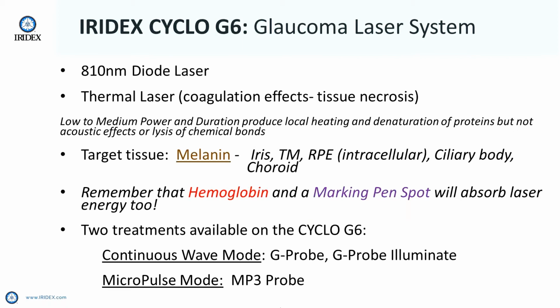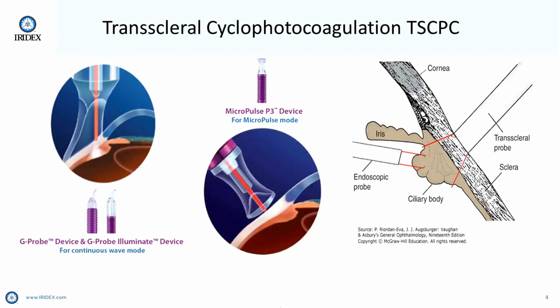There are 2 treatments available on the Cyclo G6 glaucoma laser system: continuous wave mode and micropulse mode. Transscleral cyclophotocoagulation can be delivered in 3 different ways: utilizing the delivery devices G-probe and G-probe Illuminate for the continuous wave mode, the MP3 or micropulse probe for the micropulse mode, and it can also be delivered endoscopically to all treat the ciliary body.